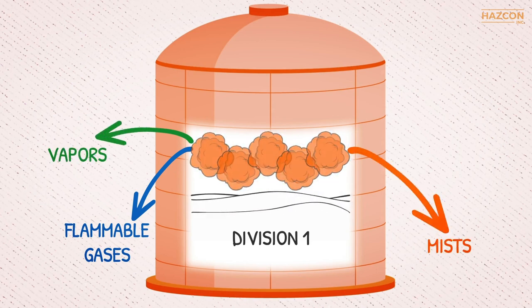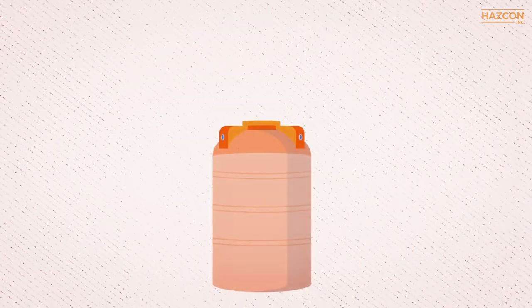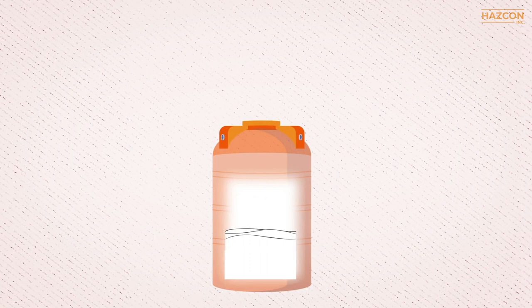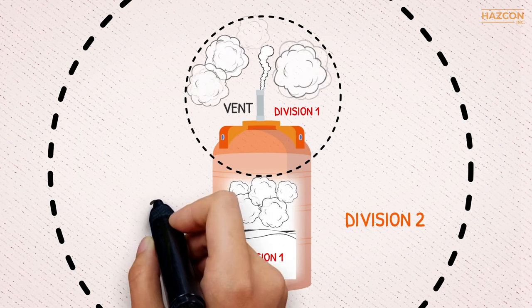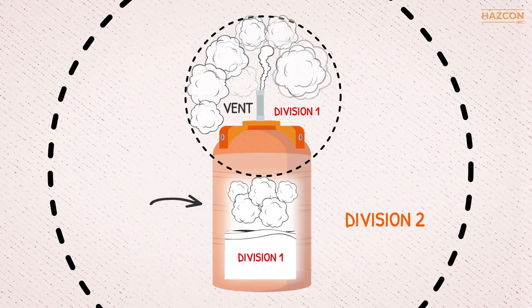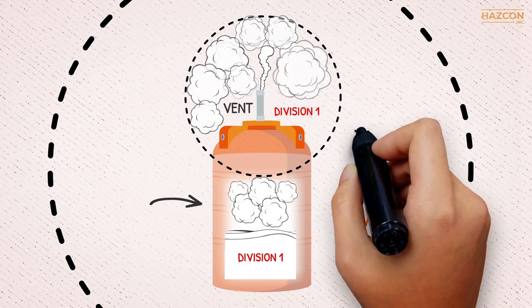Let's look together at an example of a Class 1 hazardous area. This illustration shows a gasoline tank with a fixed roof and vent. Both Division 1 and 2 locations are shown. Notice that the Division 1 location is inside the tank above the flammable liquid where a gas vapor could exist, and outside the storage tank in the area immediately around the tank's vent.